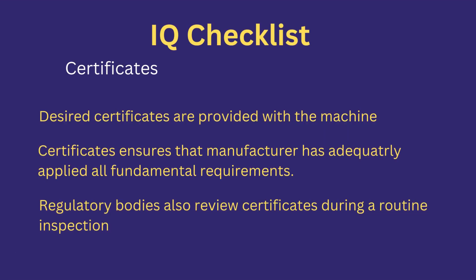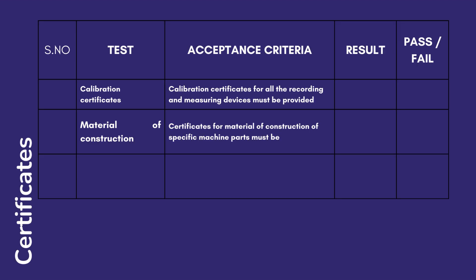Certificates are proof that the manufacturer has used the desired production specifications during manufacturing. In this test, it is verified that the desired certificates are provided with the machine. Regulatory bodies also review certificates during their routine inspection. Possible tests in this section include: Calibration certificates — calibration certificates for all recording and measuring devices must be provided. Material of construction — certificates for material of construction of specific machine parts must be provided.